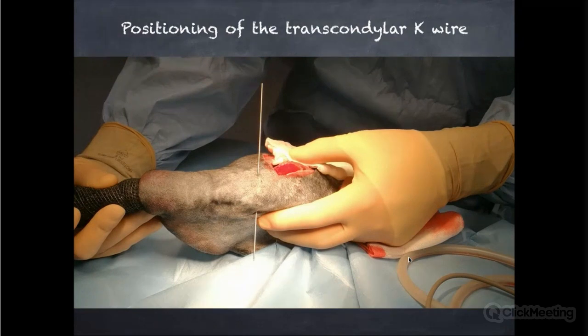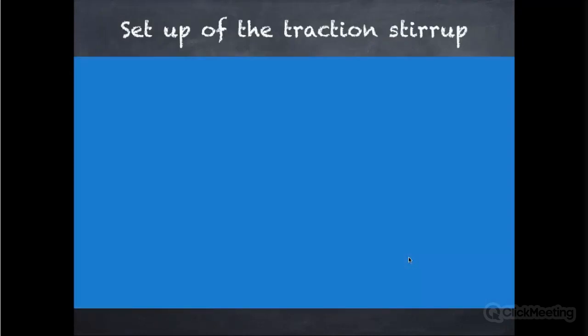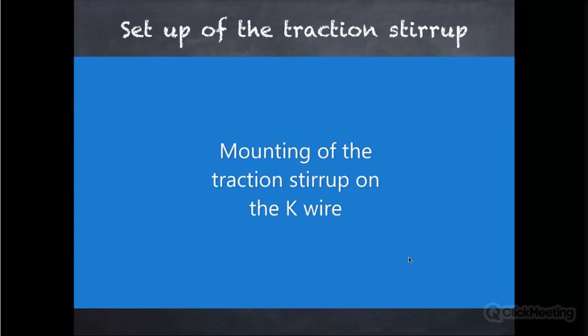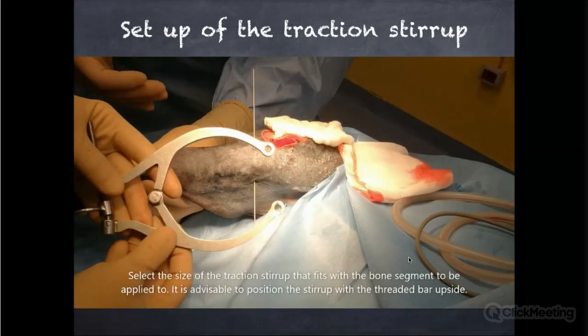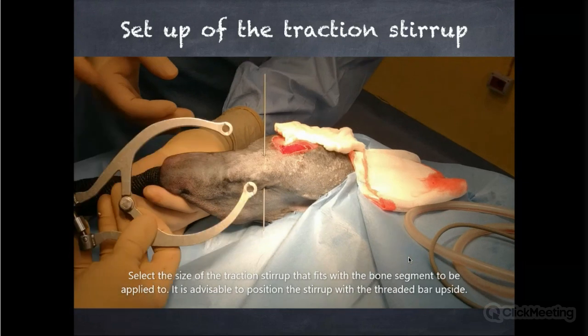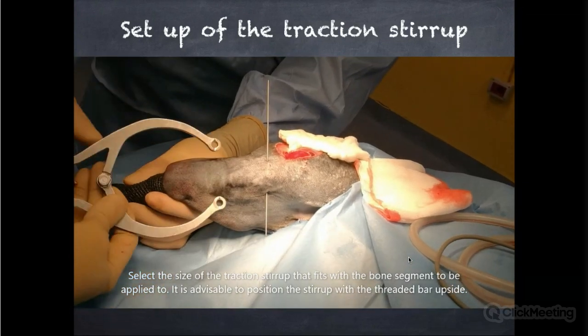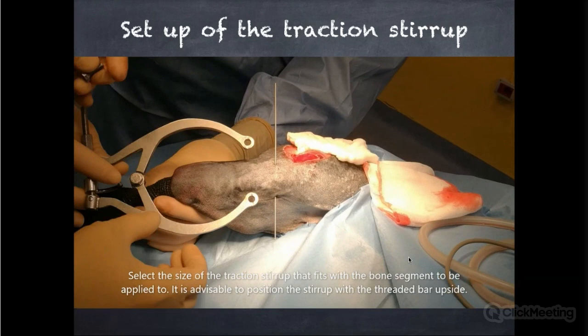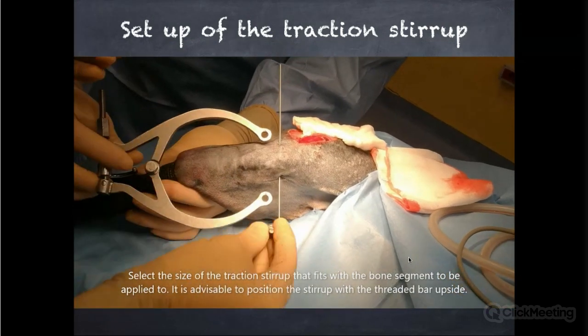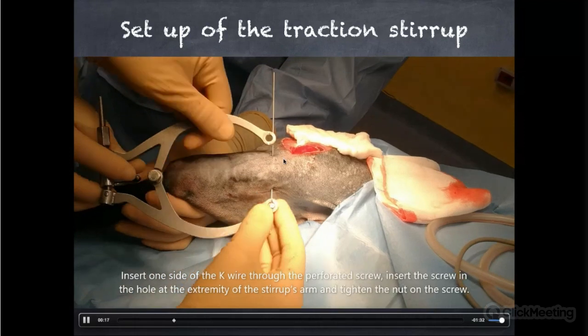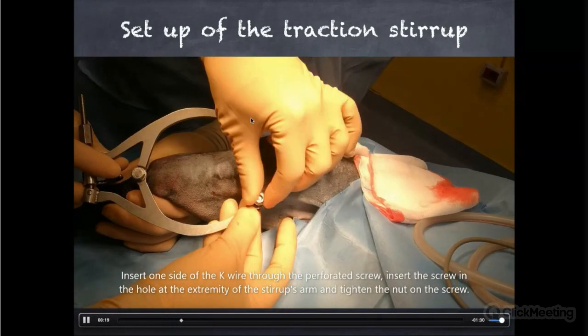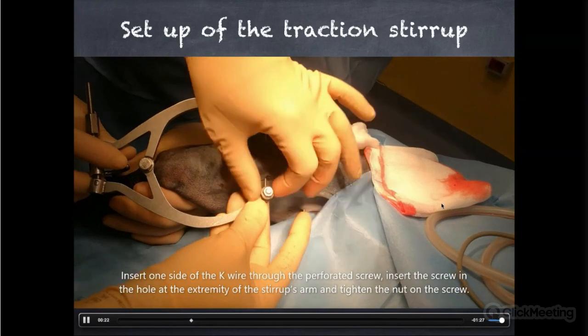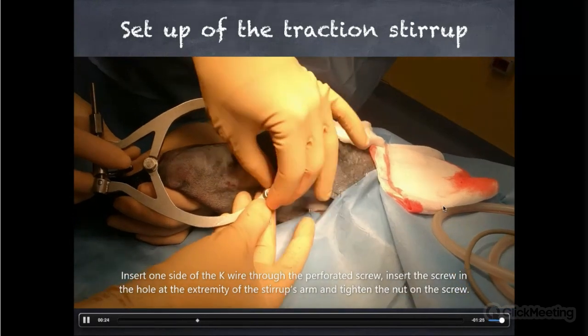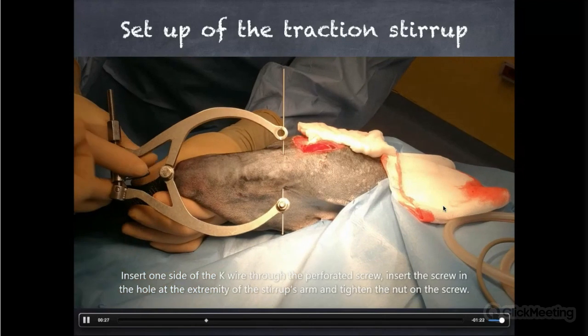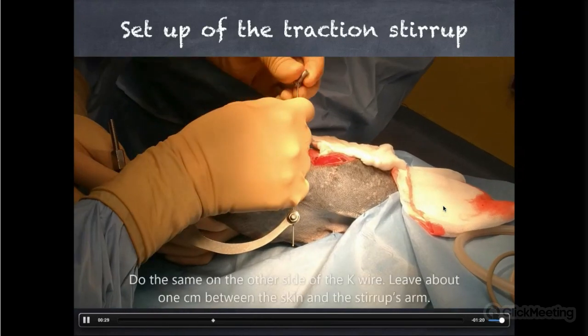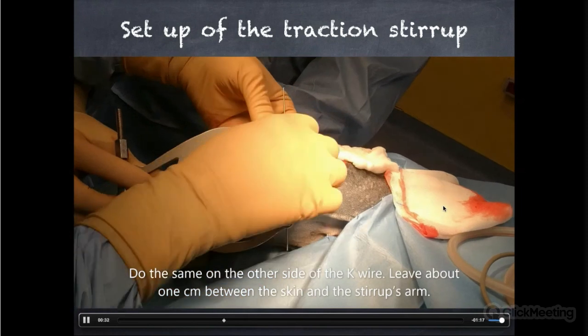Once we have the K-wire positioned like this, very straightforward, simple procedure, we can apply at this point the stirrup and set it up. We have different sizes of this stirrup. You can select the correct size of the stirrup, not too small. The opening of the stirrup should be enough for the arms to stay on both sides of the limb, but at the same time not too big. Why? Because we don't want undue interference with the fracture area.